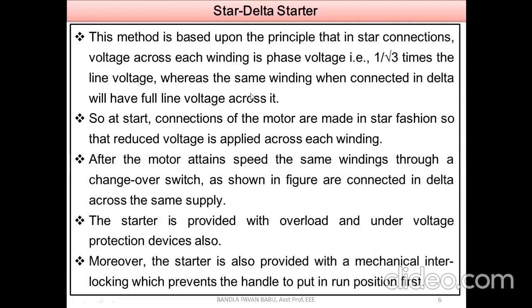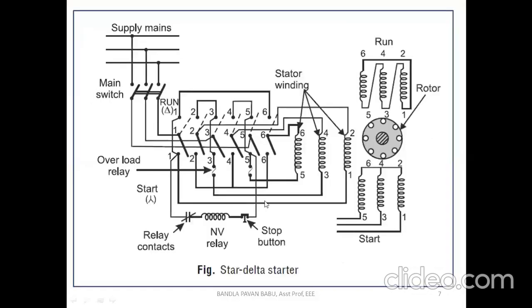So at start, connections of the motor are made in star fashion, so that the reduced voltage is applied across each winding. After the motor attains speed, the same windings, through a changeover switch as shown in the figure, are connected in delta across the same supply. So let us see here.